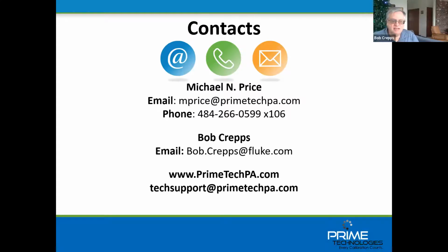Is there any value loss with the 753 specifically when dealing with calibrations with ProCal? Good question. Yeah, the 753 and 754 are the exact same device, except the 754 adds HART capability. So you can talk to most every HART device and get the basic HART communication calibration-wise. And it also supports some of the most common HART transmitters.